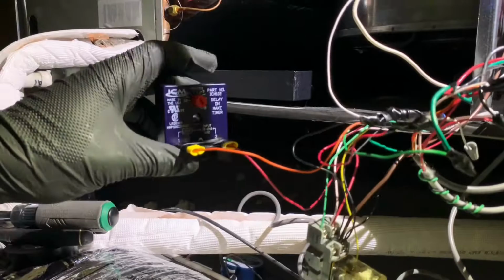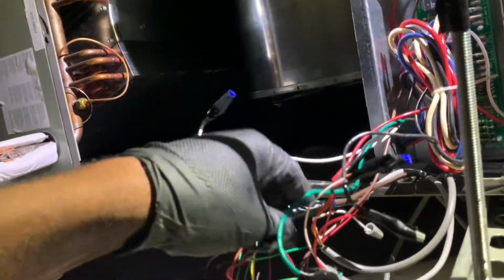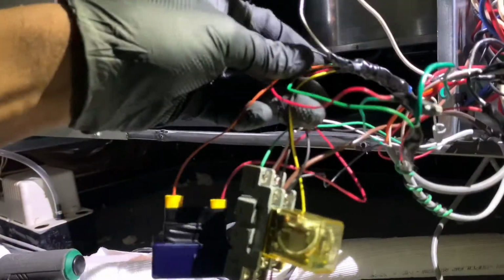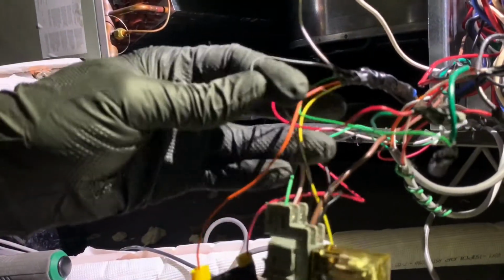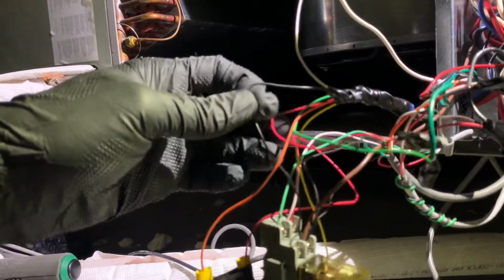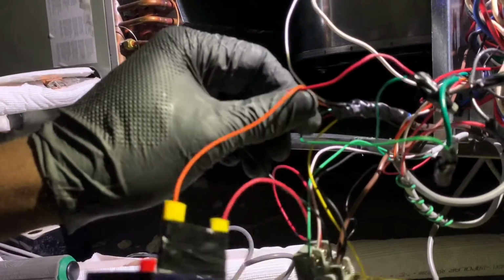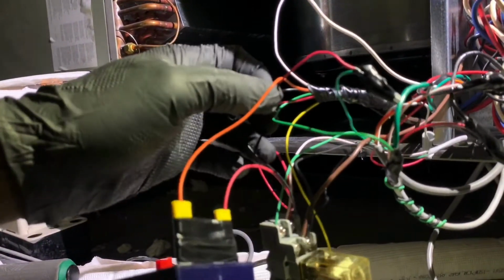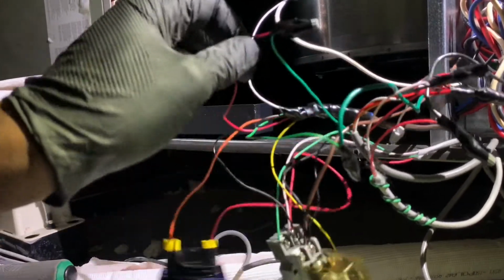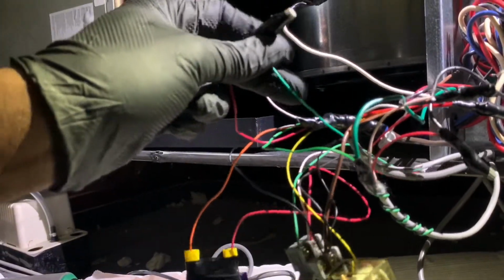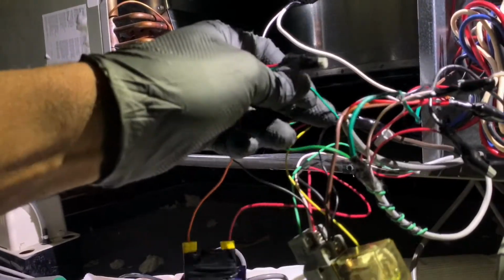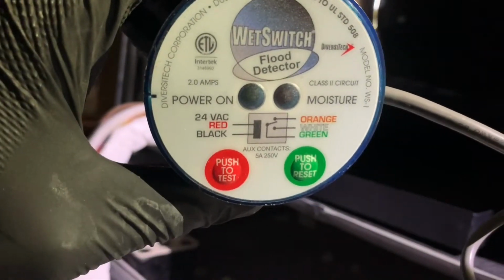All right, so here's the juicy stuff. So let me start with the thermostat. Well, this here is my thermostat wire. See black here. That goes to common. Red is 24 volts hot. And if you notice, the 24 volts hot for the thermostat is coming out of a green wire. Well, this green wire is basically the green wire for this device right here.